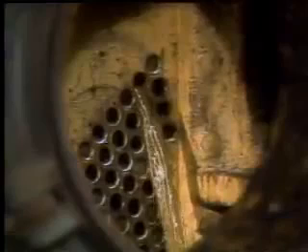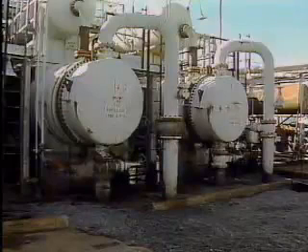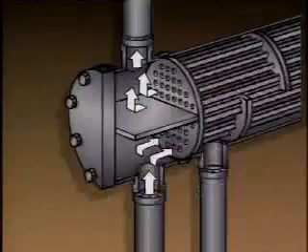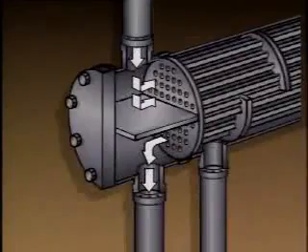However, these methods require the heat exchanger to be shut down and taken apart. In some heat exchangers, cleaning can be accomplished using a technique called backwashing. Backwashing is the reversing of flow through the heat exchanger. This technique is effective in temporarily dislodging materials from the ends of the tubes and the tube sheets.